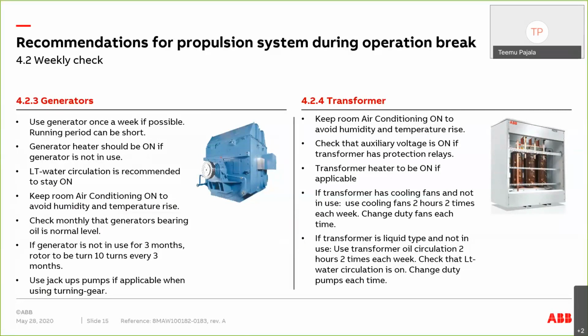Transformers are a little bit easier. There are not many moving parts, but there is winding, and that winding requires that the humidity does not increase too much and get the winding wet. That's why heaters should be in use, and the transformer cooling fans should be run for about 2 hours, 2 times a week, which is good practice.